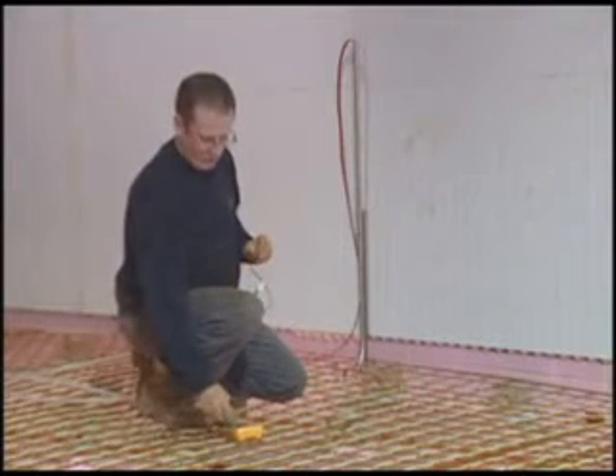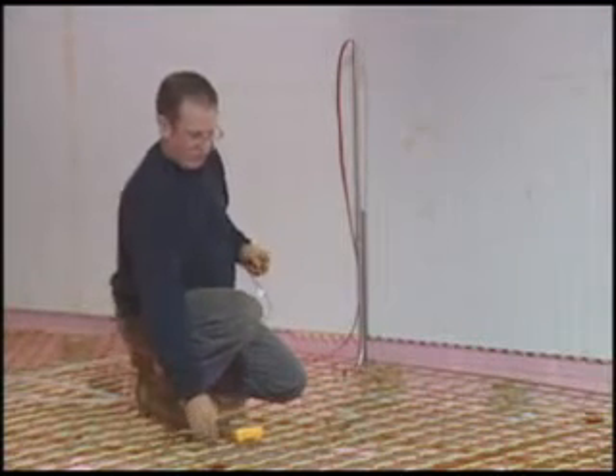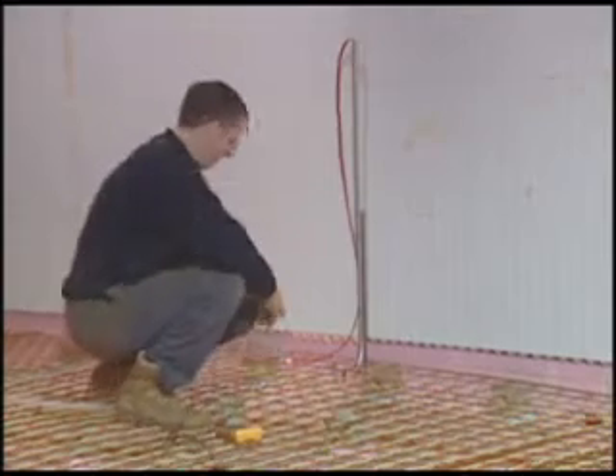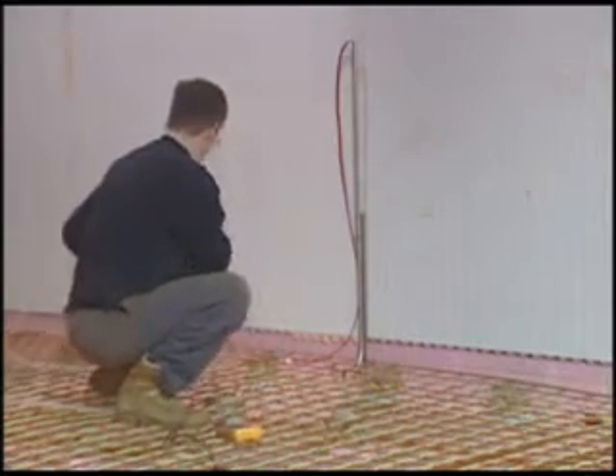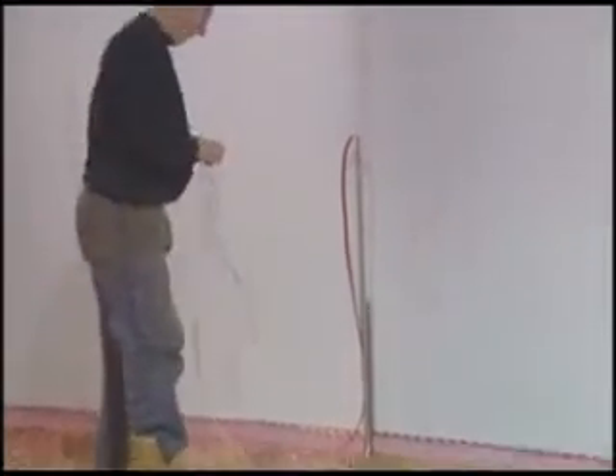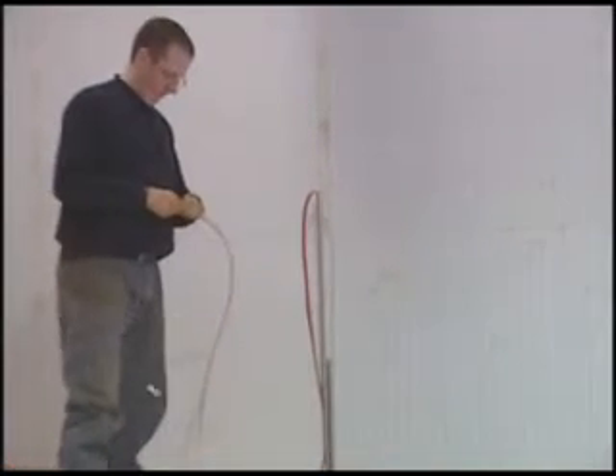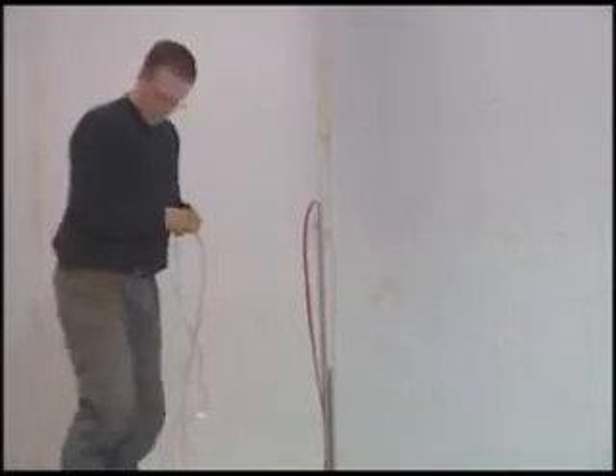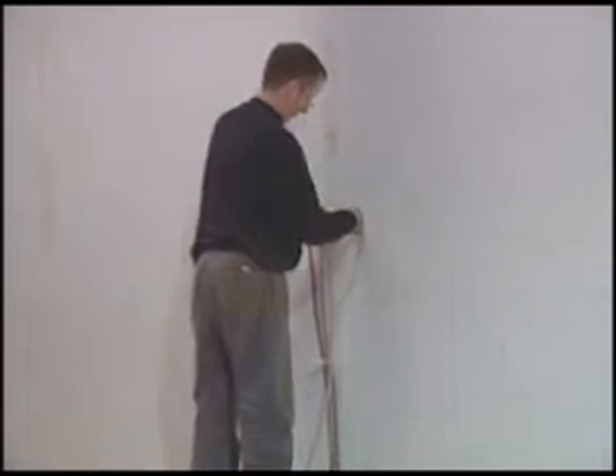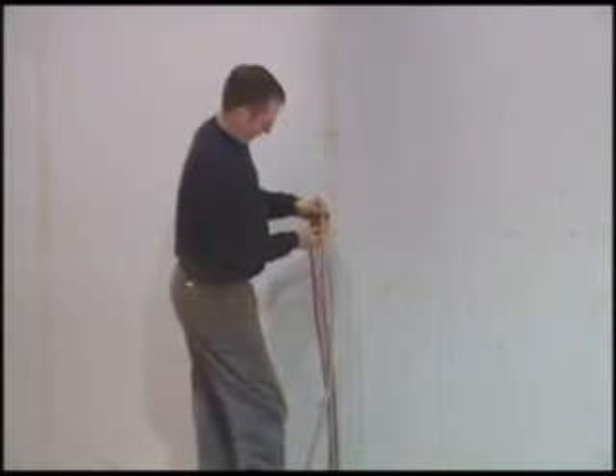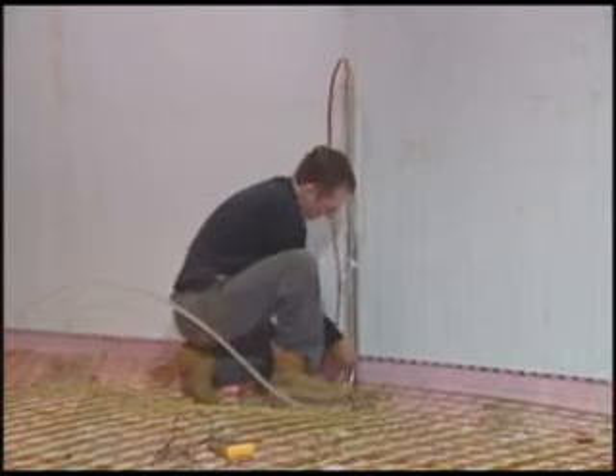You can now install the floor temperature probe. Use a multimeter to check the probe's integrity. Connect the multimeter to the probe and measure its resistance. This should correspond to the data on the probe label. Take the protective sleeve and slide the probe's end into it. Insert the probe so that the capillary reaches the bottom end of the sleeve.